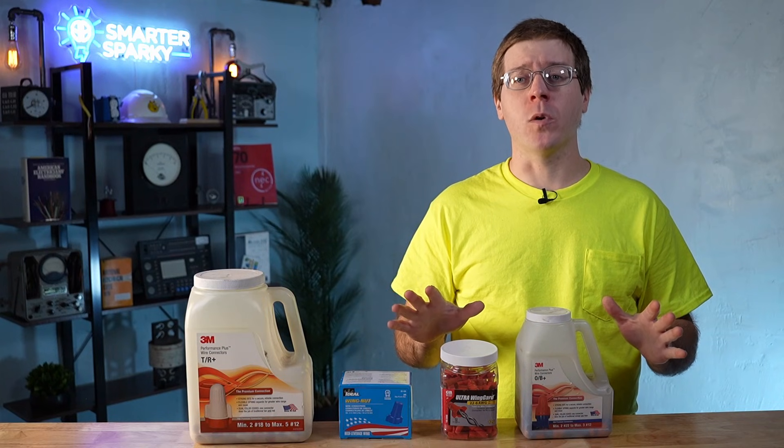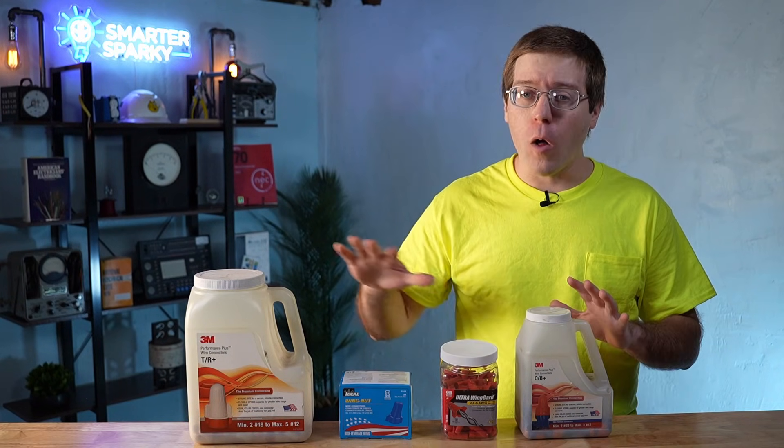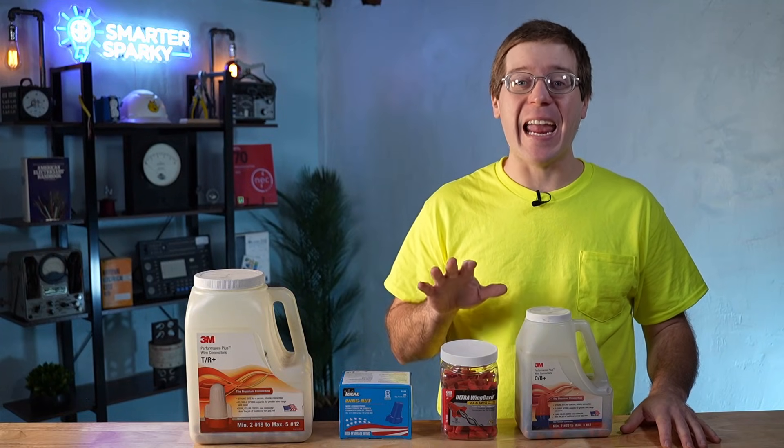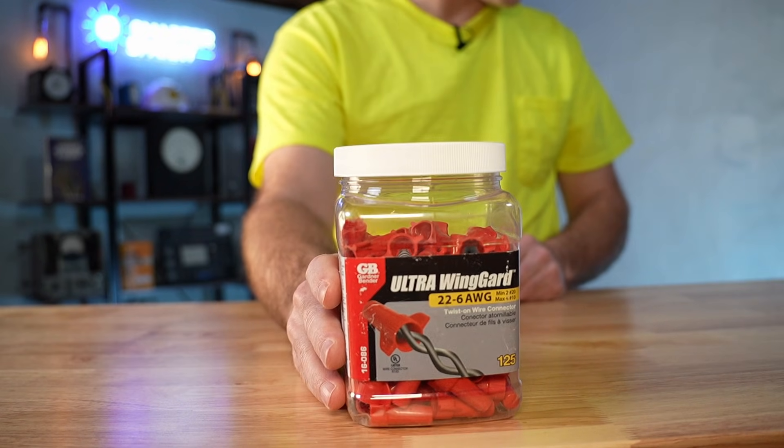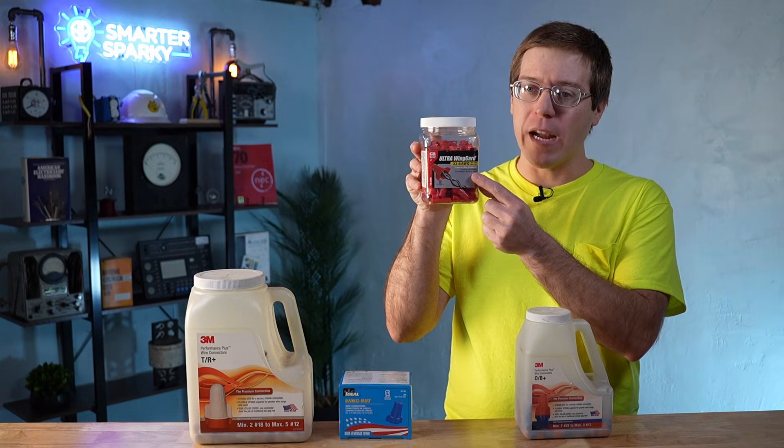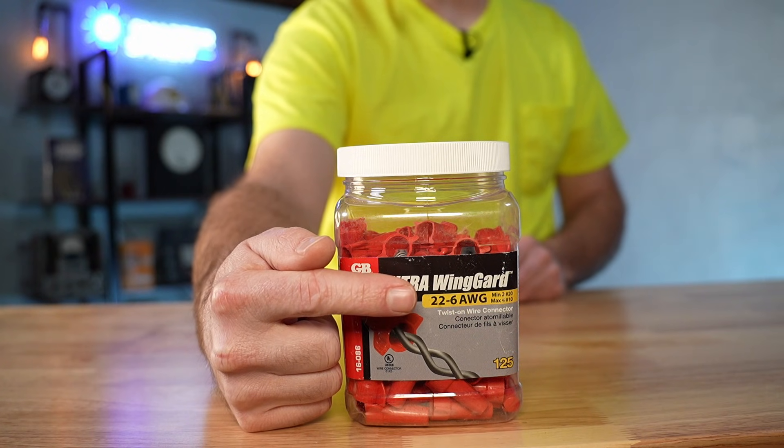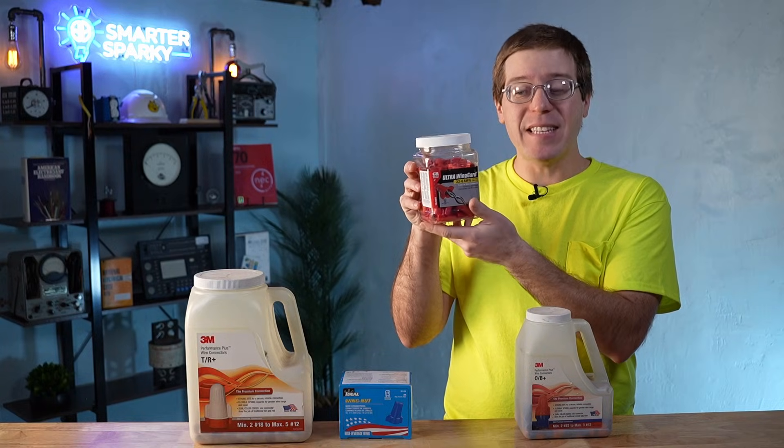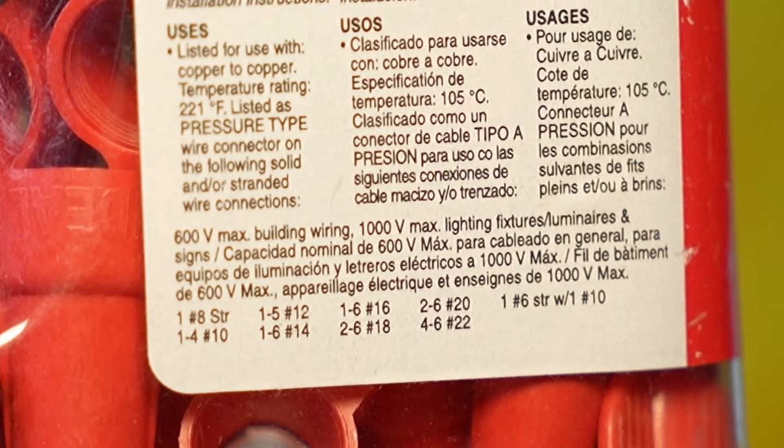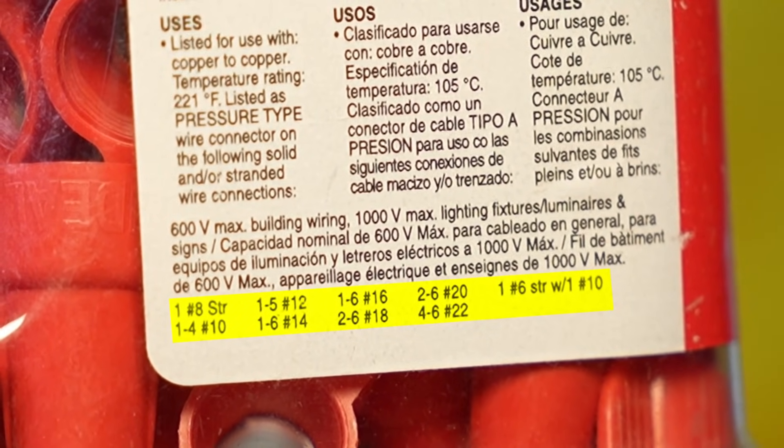The most perfect splice in the world will still fail if you use the wrong wire nut. All wire nuts have a range of wire sizes and conductor quantities that they can work with. Here's a box of wire nuts from the local big box store. Right on the front, we can see these wire nuts are good from 22 gauge, the smallest, to 6 gauge, the largest. Listed on the side of the packaging, however, it shows all of the wire combinations that the wire nuts are approved for.